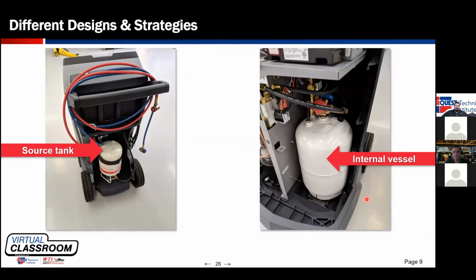Yes, I can speak for both of the machines that I have used. After you evacuate the system, the machine makes you pause and do the evaporator leak test or the vacuum decay leak test. And then it prompts you to go step by step through the evaporator leak tests. So it's not something that you as a tech have to remember, oh, I've got to do this. The machine physically isn't going to let you proceed without doing it. And it does have these step-by-step menus for how to do it, at least the ones that I have used.